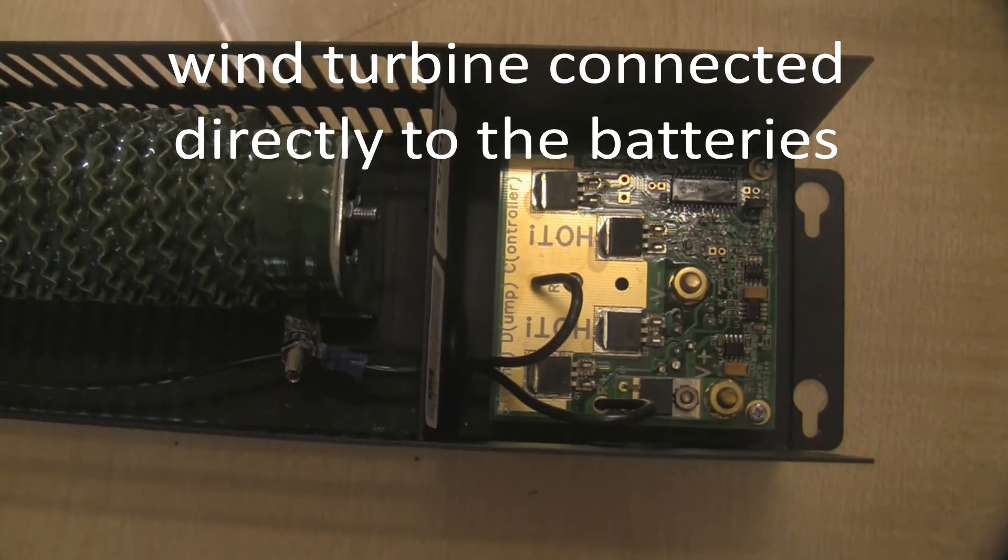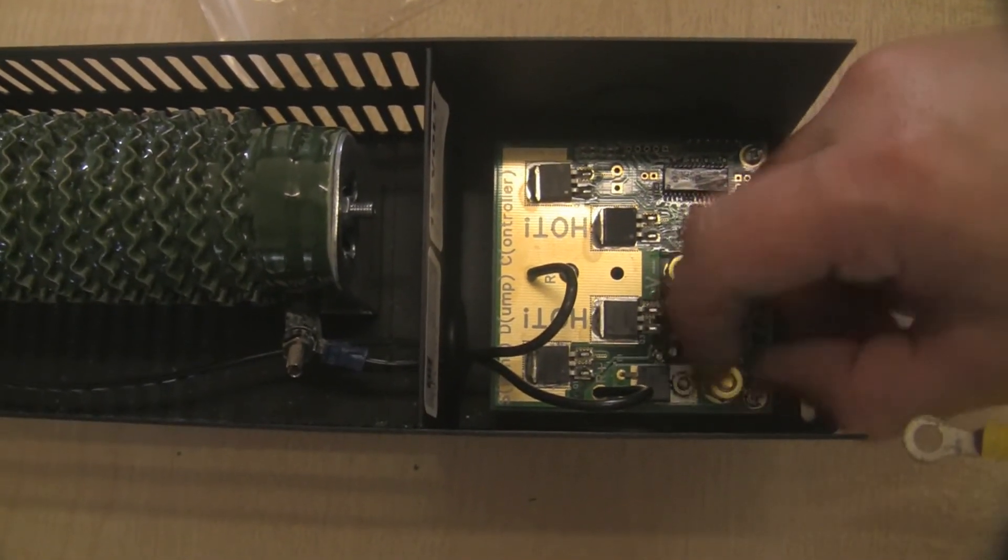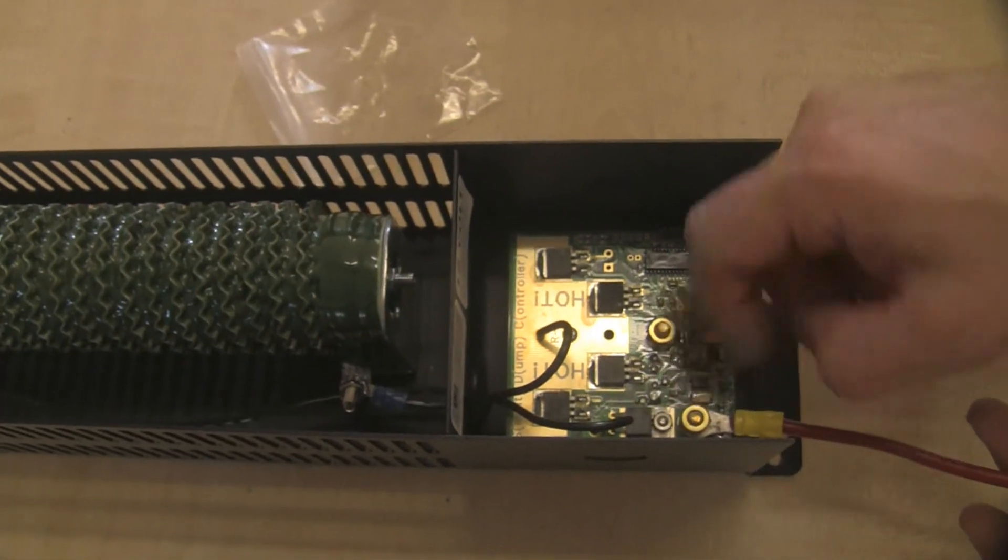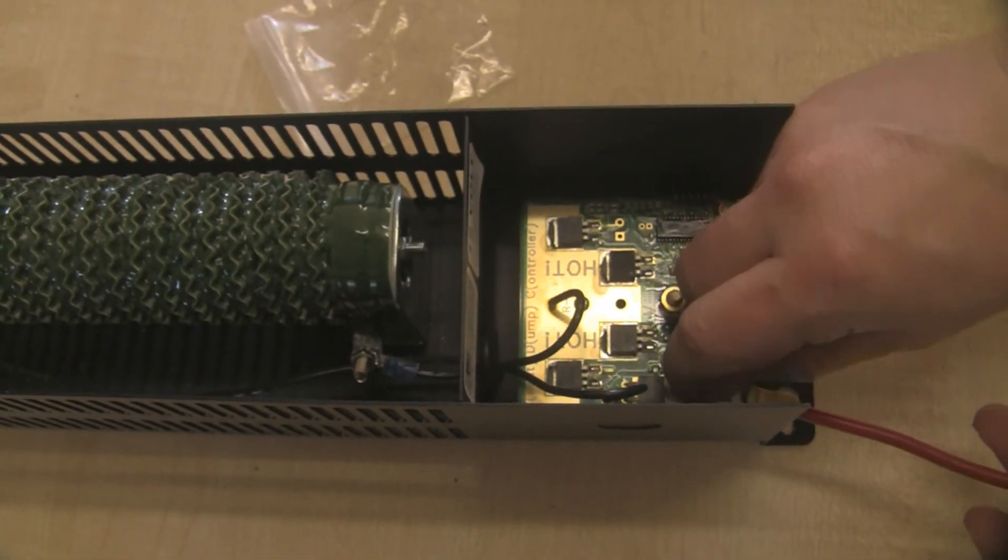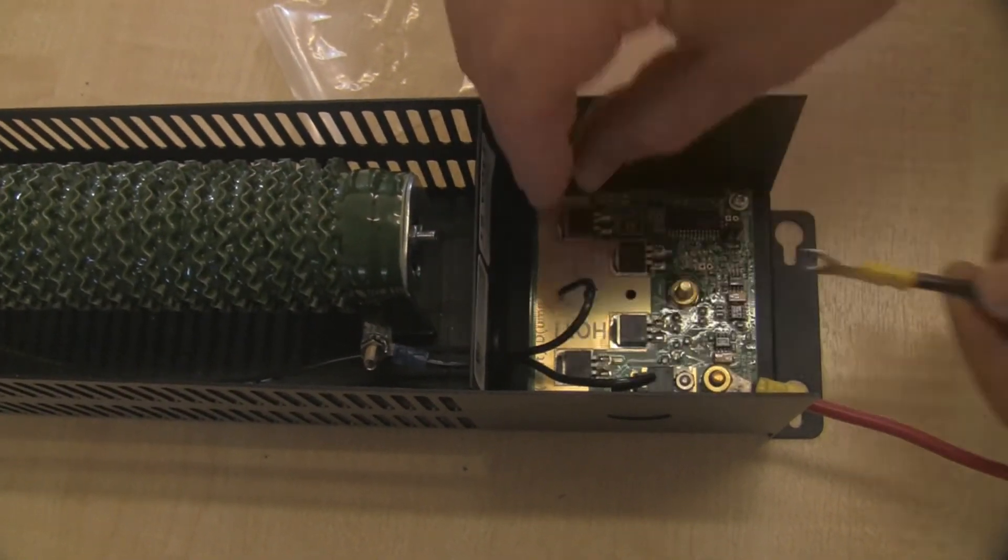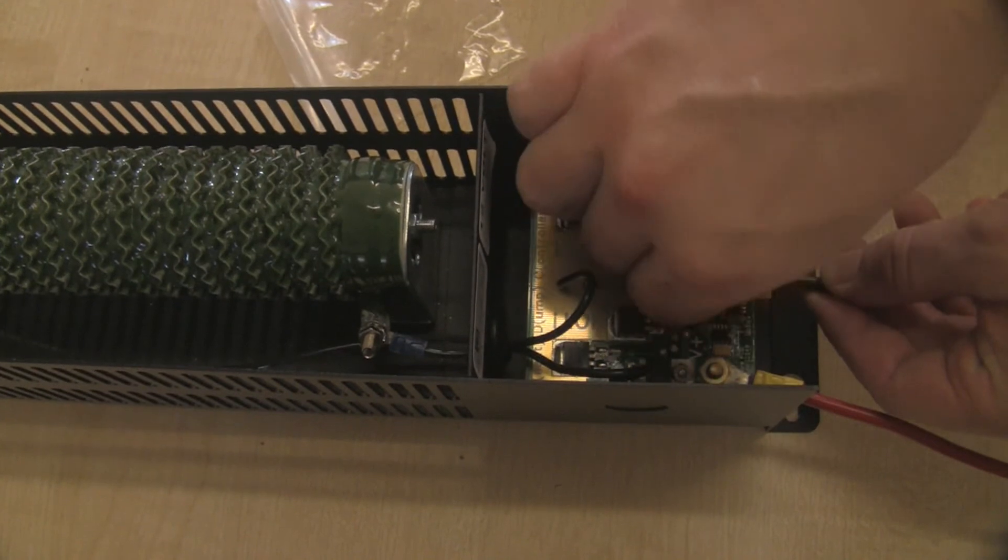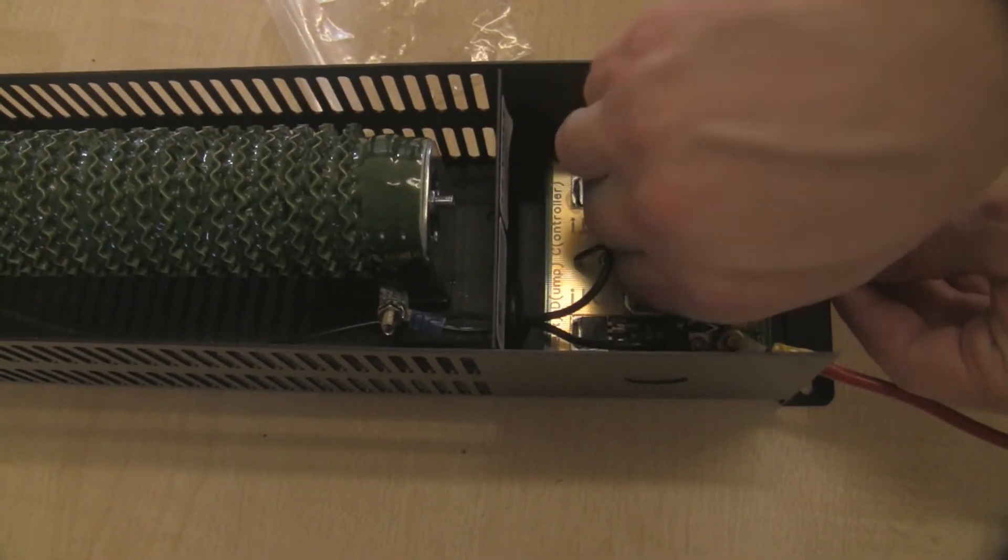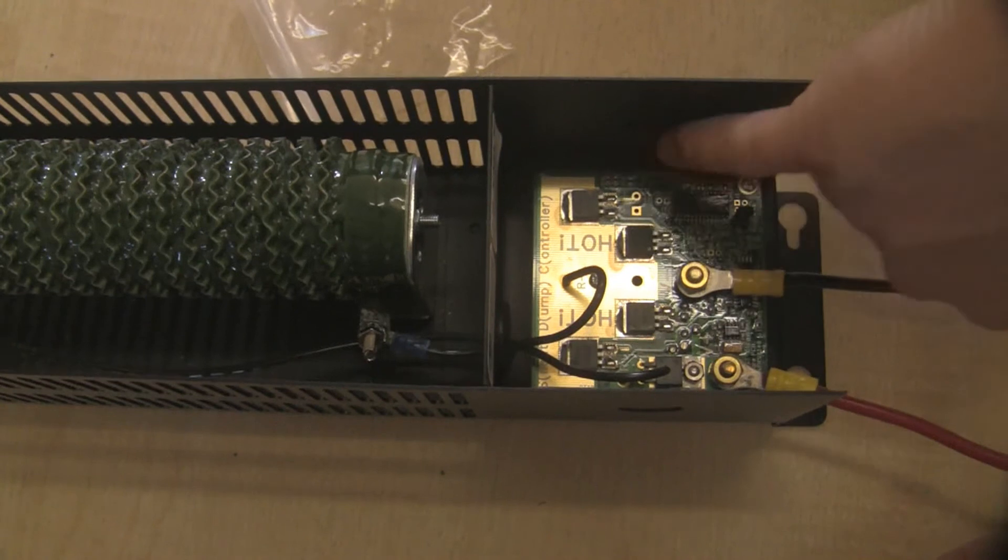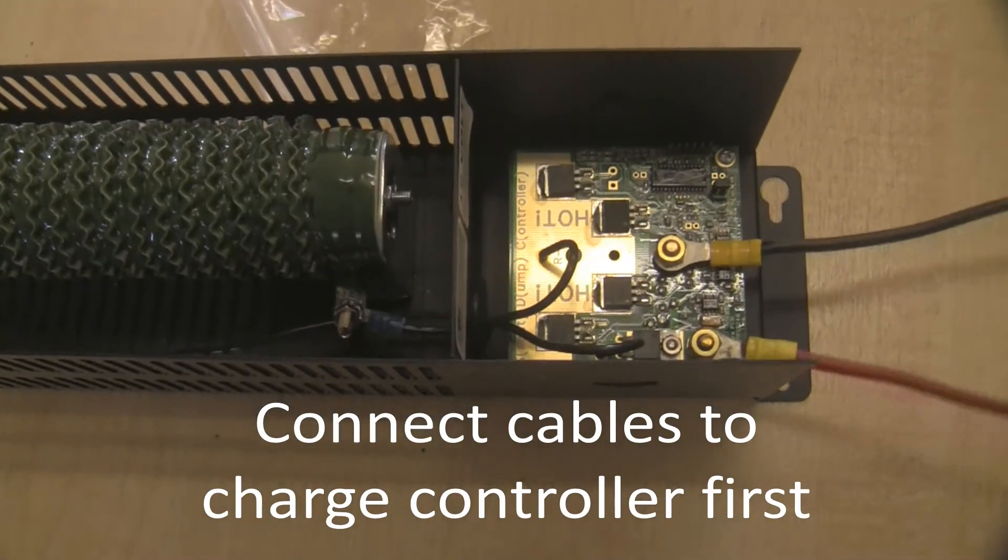So I've prepared some cables earlier, a red cable for the positive. I'll put some ring crimps on here. Make sure you use the correct size. I won't do these up particularly tight as it's just a demonstration. And then the negative cable connects to that section of the circuit board. Now you do need to be careful when you tighten these up with spanners and sockets; you don't over tighten these fixings otherwise you can damage the circuit board. And one other thing to bear in mind is these cables would usually come out of the cable gland hole through the grommet or the cable gland that we fitted there. But in this case we're simply just running the cables out of the bottom there.